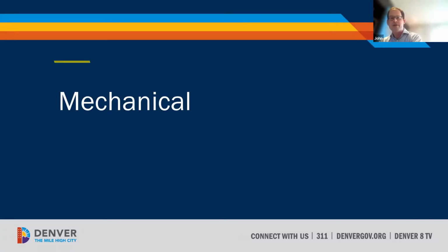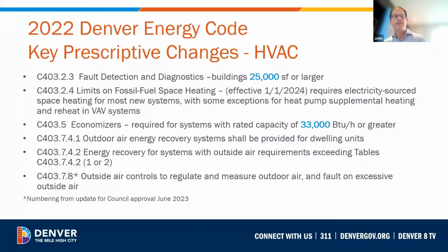For the mechanical, for this purpose, this covers the heating and cooling systems as well as ventilation systems for the project. A summary of the Denver Energy Code prescriptive energy changes. One of the new changes is fault detection diagnostics are now required for buildings of 25,000 square feet or larger. Now, for some of the smaller buildings that use packaged equipment, these control options can often be embedded in the system controllers that are available as an option for these systems. There are limits on fossil fuel and space heating, and these are effective January 1st, 2024. They require electrically sourced space heating for most new systems. There are some exceptions for heat pump, supplemental heating, and reheat.